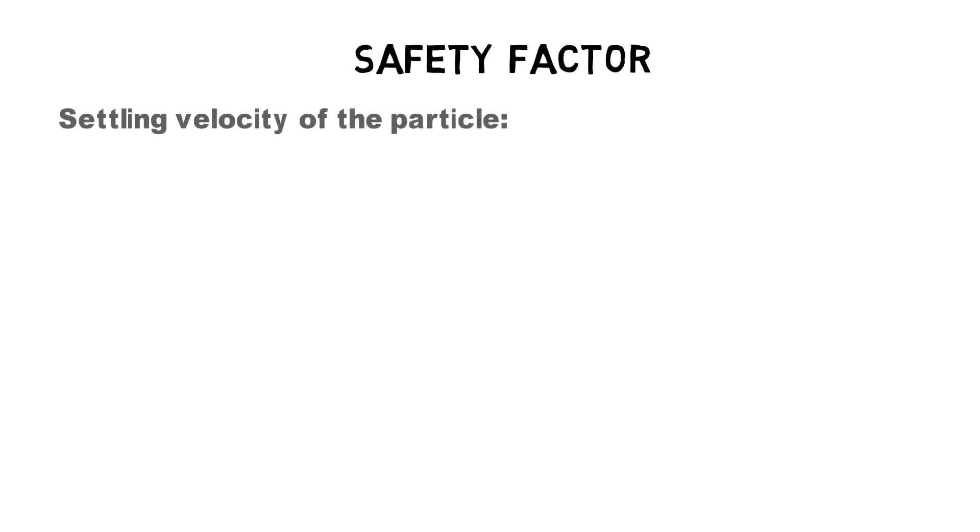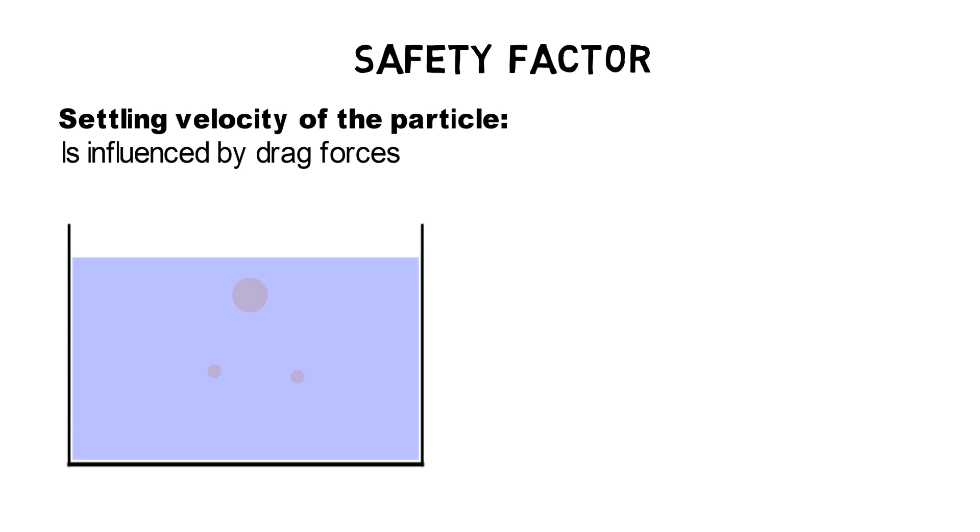Stokes Law assumes laminar flow, no other colliding particles and other factors, but since we want to design a sedimentation tank, we have to consider an additional safety factor. Depending on the retention time and water turbidity, different safety factors can be applied, but we'll use a safety factor of two.